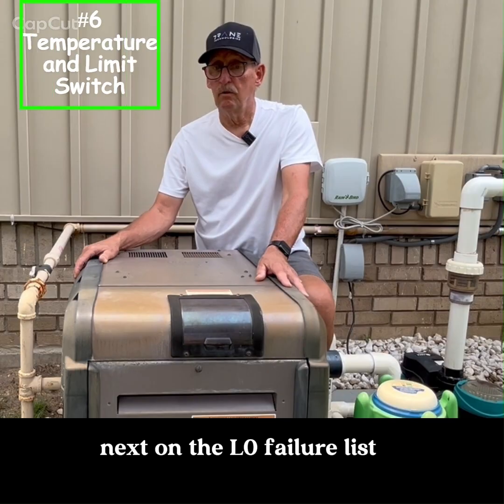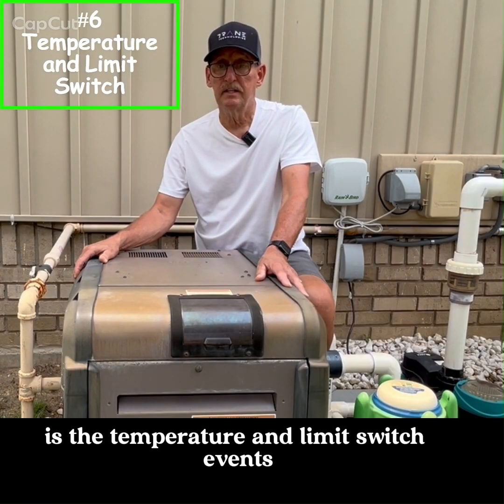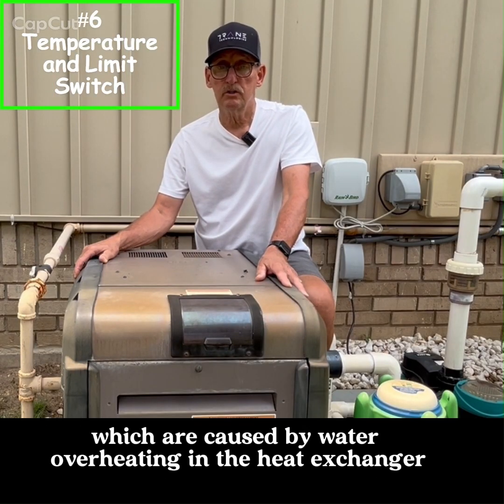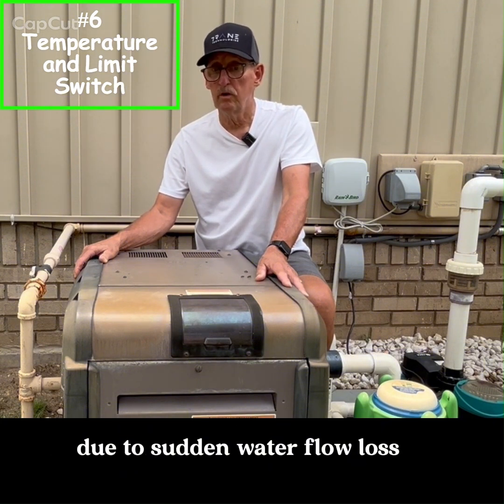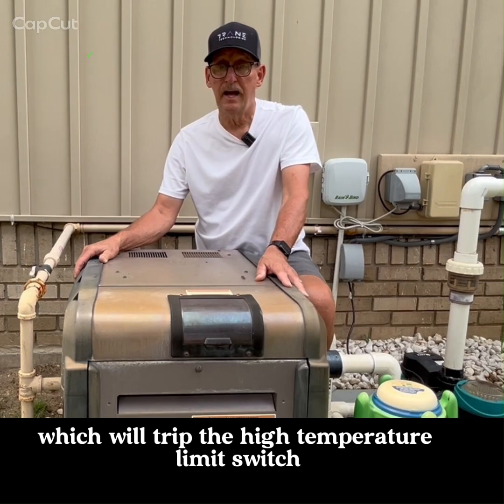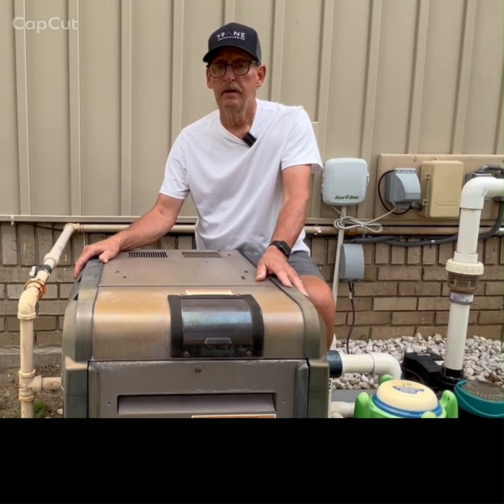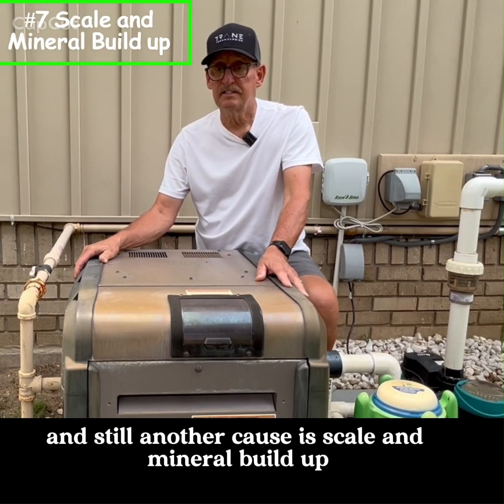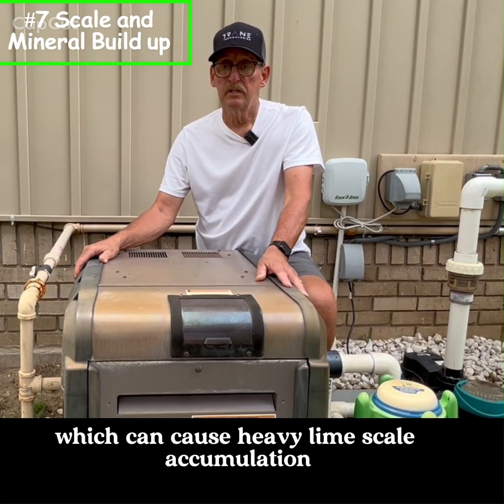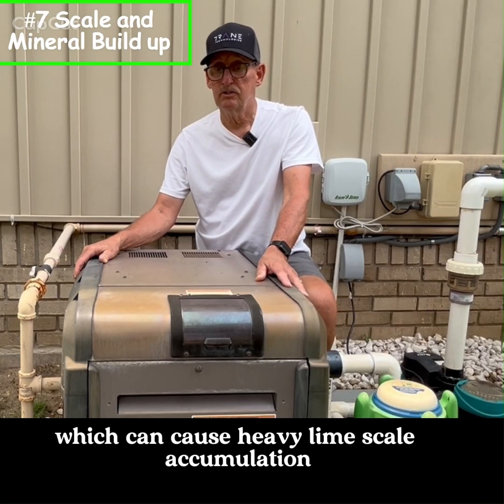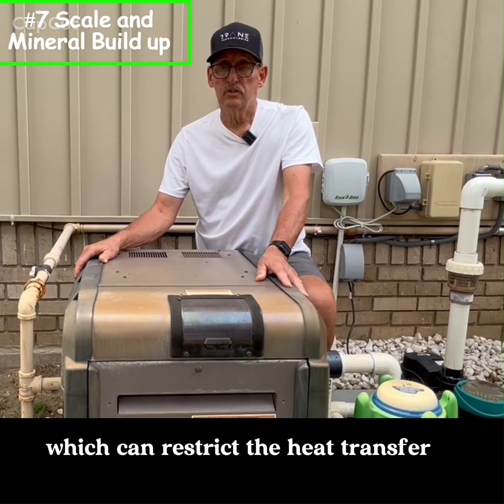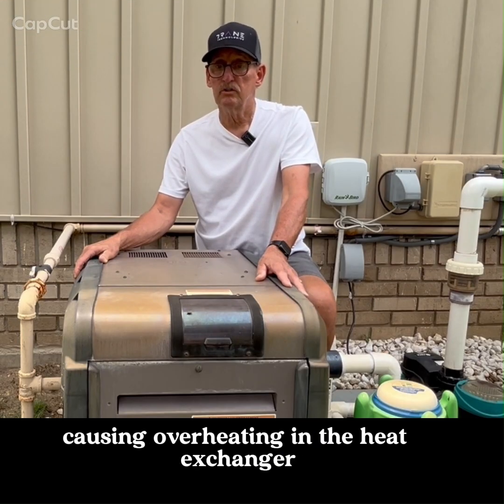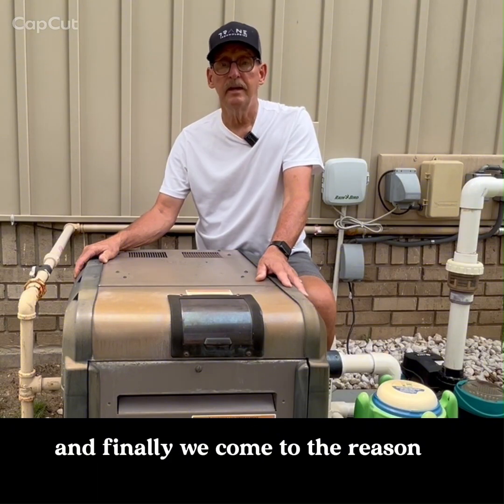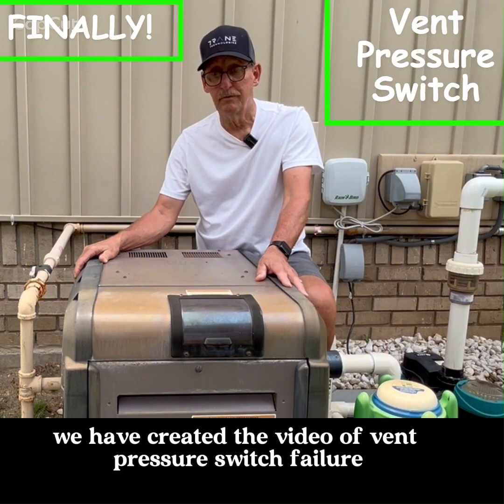Next on the LO failure list is the temperature and limit switch events, which are caused by water overheating in the heat exchanger due to sudden water flow loss, which will trip the high temperature limit switch. And still another cause is scale and mineral buildup, which can cause heavy lime scale accumulation inside the heat exchanger, which can restrict the heat transfer, causing overheating in the heat exchanger. And finally, we come to the reason we have created the video, a vent pressure switch failure.